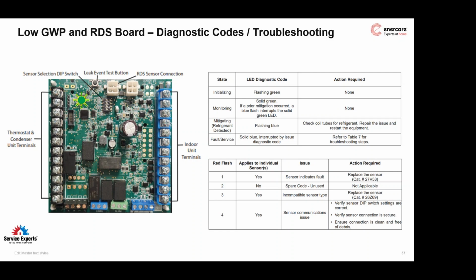Otherwise, they'll still have some of their heat or some of their cooling. It will still function, only if the sensor itself is faulty. Otherwise, if there is a leak, then no, they'll lose their heating, they'll lose their cooling. And then once this sensor has determined that it's below the lower flammability limits, somewhere between 5 and 7 minutes, it will run the fan at the end of that dissipation, and then go back to normal operation.